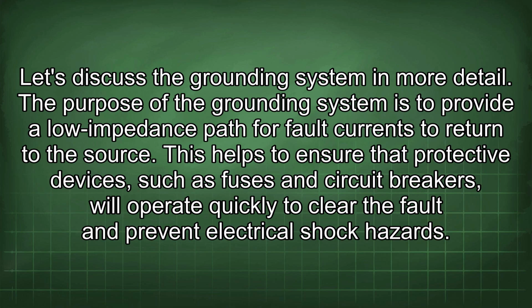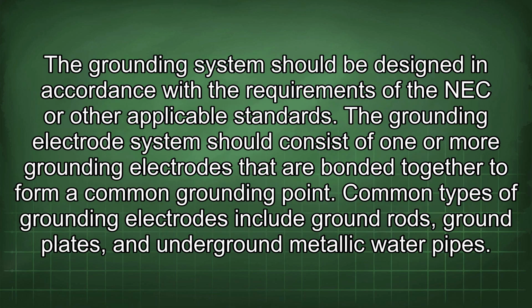The purpose of the grounding system is to provide a low impedance path for fault currents to return to the source. This helps to ensure that protective devices, such as fuses and circuit breakers, will operate quickly to clear the fault and prevent electrical shock hazards. The grounding system should be designed in accordance with the requirements of the NEC or other applicable standards.